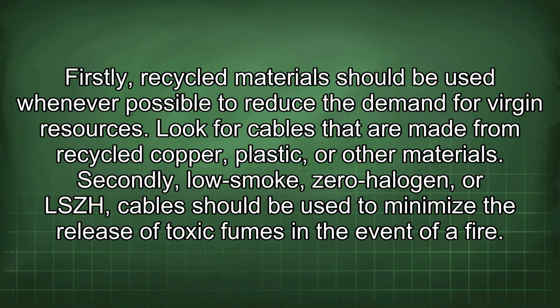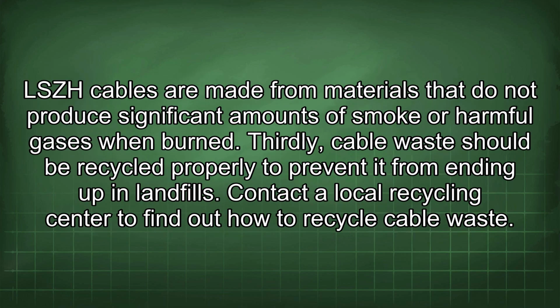Secondly, low smoke, zero halogen, or LSZH cables should be used to minimize the release of toxic fumes in the event of a fire. LSZH cables are made from materials that do not produce significant amounts of smoke or harmful gases when burned. Thirdly, cable waste should be recycled properly to prevent it from ending up in landfills. Contact a local recycling center to find out how to recycle cable waste.